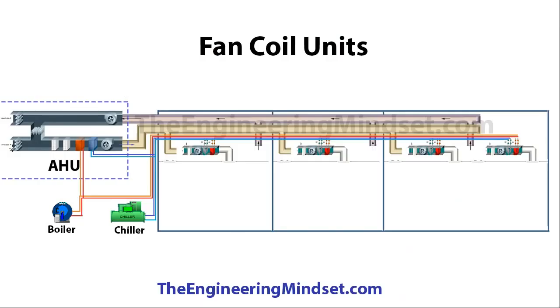The main AHU supplying all the fresh air for the building does not necessarily need additional heating and cooling coils — it could just be 100% fresh air being pushed in and out, with perhaps just filters on the supply. You would still have connections to chillers and boilers feeding the fan coil units, unless cooling is supplied by a refrigeration unit and heating is electric.